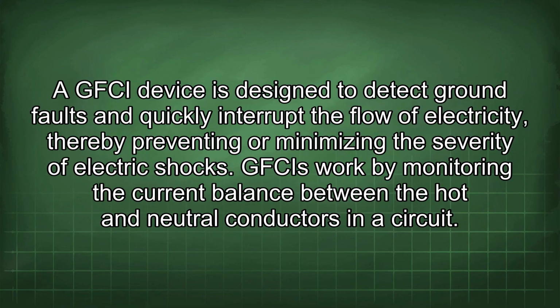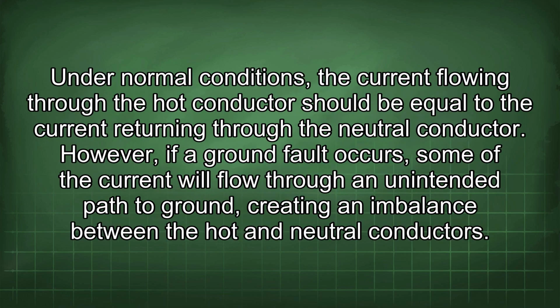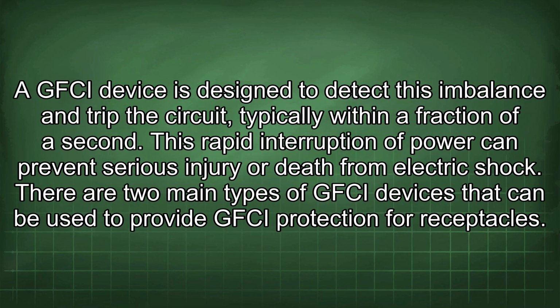A GFCI device is designed to detect ground faults and quickly interrupt the flow of electricity, thereby preventing or minimizing the severity of electric shocks. GFCIs work by monitoring the current balance between the hot and neutral conductors in a circuit. Under normal conditions, the current flowing through the hot conductor should be equal to the current returning through the neutral conductor. However, if a ground fault occurs, some of the current will flow through an unintended path to ground, creating an imbalance between the hot and neutral conductors. A GFCI device is designed to detect this imbalance and trip the circuit, typically within a fraction of a second. This rapid interruption of power can prevent serious injury or death from electric shock.